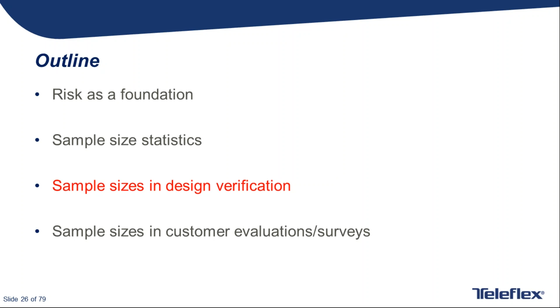This is the classic medical device design model that I'm sure many of you have seen. New product development or improvement begins with identifying what the user or customer wants. Then, in design inputs, the customer needs are translated to requirements. During the design process, outputs are produced, which should be traceable back to the design inputs through verification. Verification answers the question whether the product has been designed right or as planned. Validation is different. It answers the question whether the right product was designed, or does the product trace back to and meet the user needs.